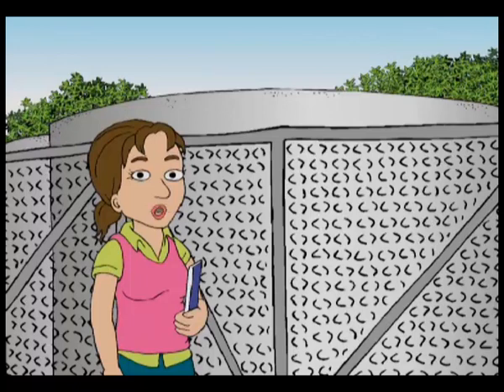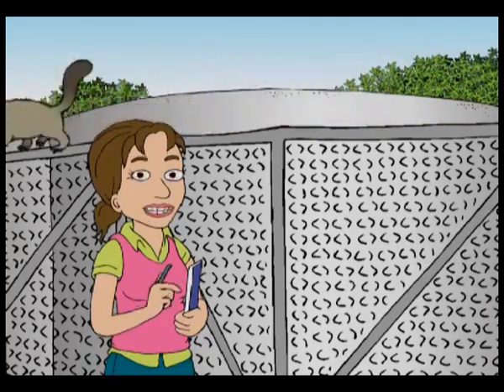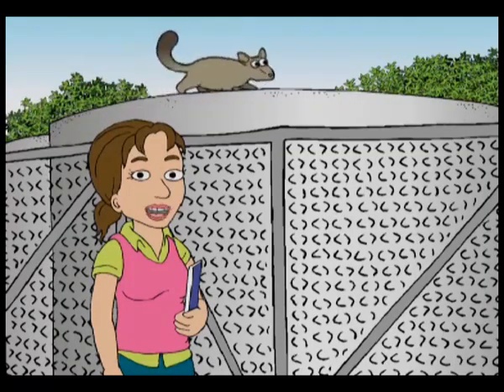It's important to choose a site for a storage tank which is still accessible during floods and other hazards, and easy to access for maintenance. Fencing, padlocks, other security measures also need to be thought about. Lids need to have a lip in order to prevent ingress. They also need to be padlocked to keep intruders out.